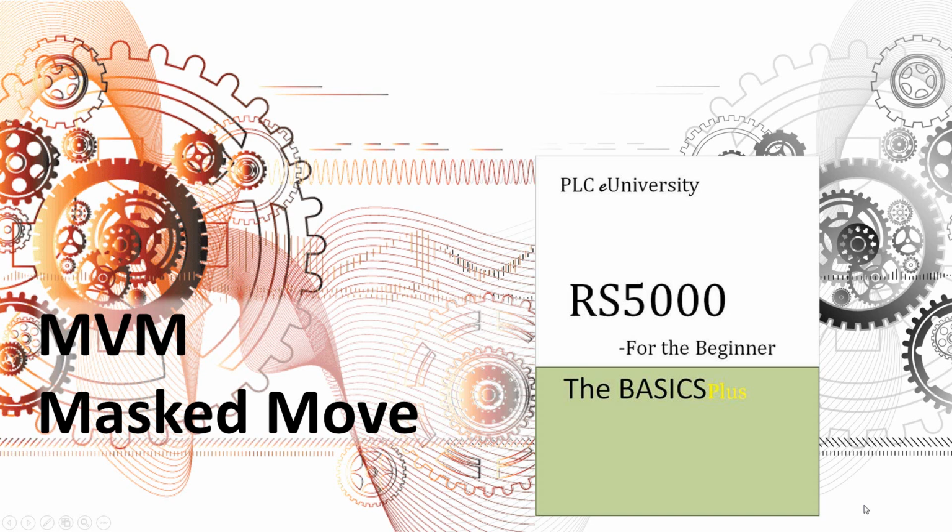The next instruction covered in the manual was the move with mask. We always try to avoid this instruction because it's hard for people to troubleshoot, because it's not real apparent what's going on. And every time you go to troubleshoot it, you have to go to the instruction help files and read about it and then go back and start analyzing it.